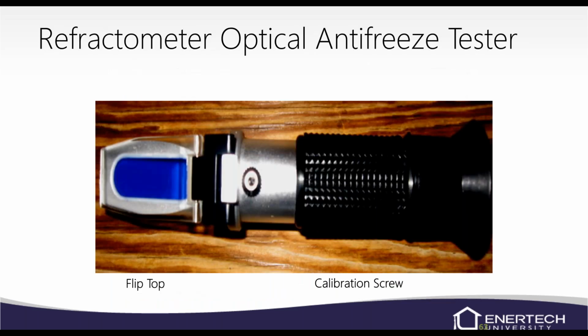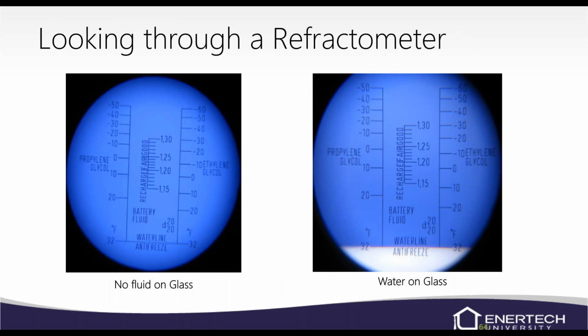Again, it makes it real easy when you have a refractometer. That little blue area there is a little door. Flip that up, put a drop on there, and then you just look through the sight glass. Now, I just had water on it. You can see with nothing on it, the whole screen is blue. I put just a regular drop of water from a water bottle, and obviously water freezes at 32, so you can see the line right there. That's also how you can calibrate this sight glass. It's got a little calibration screw on it. You just put a drop of distilled water on there, and it should go right to the 32-degree mark. But as you can see, it's got propylene glycol and ethylene glycol, and it'll tell you your freeze protection based on the line level there.